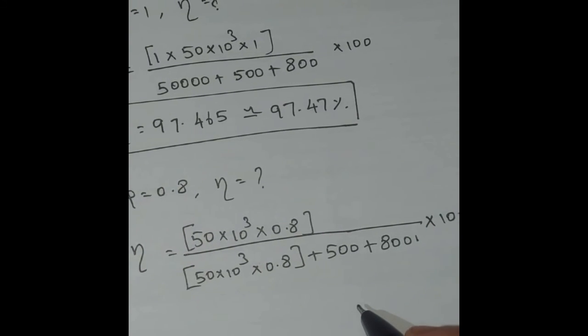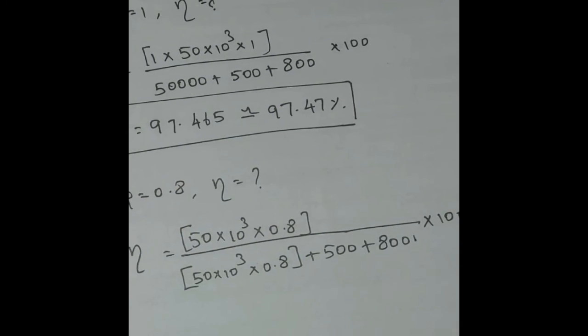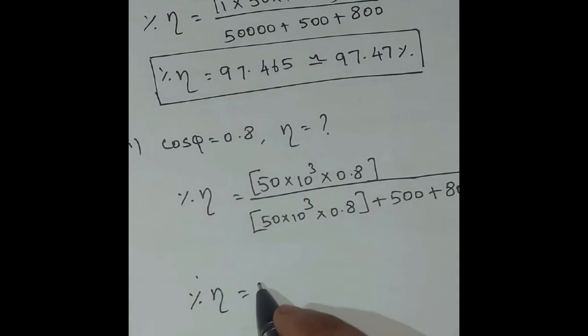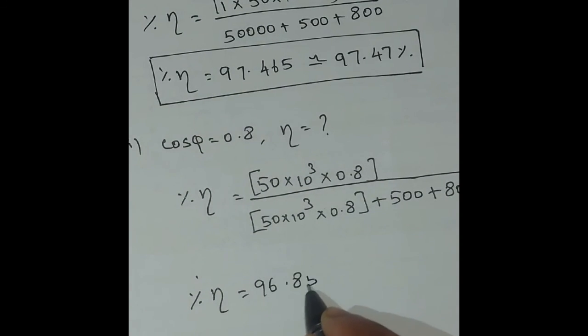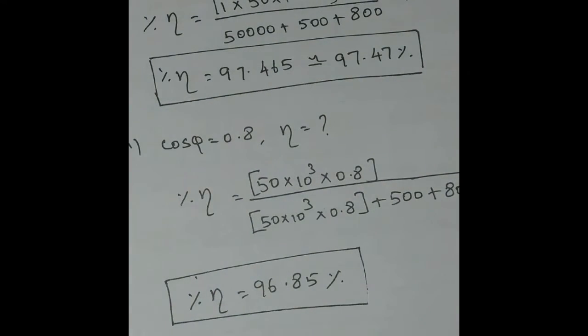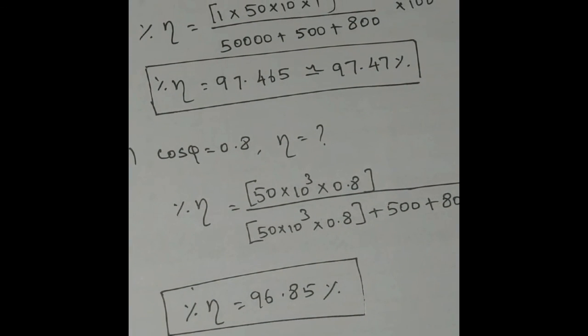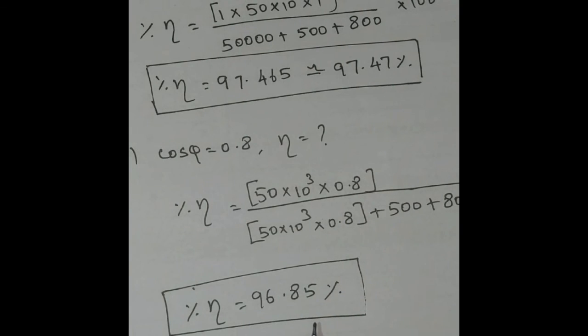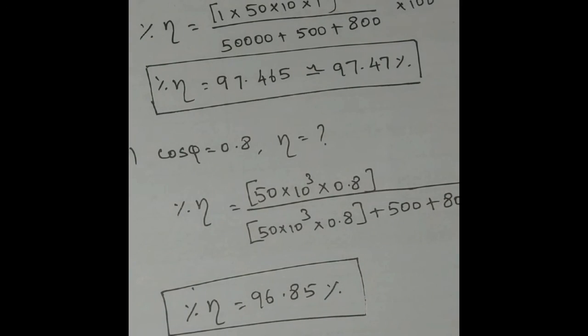Solving gives percentage efficiency of 96.85%. Comparing both cases: when power factor is unity, the efficiency of the transformer is higher; when power factor is reduced to 0.8, efficiency decreases. Therefore, it is necessary to maintain the power factor close to unity. Thank you all.